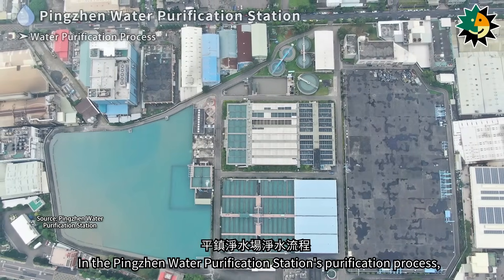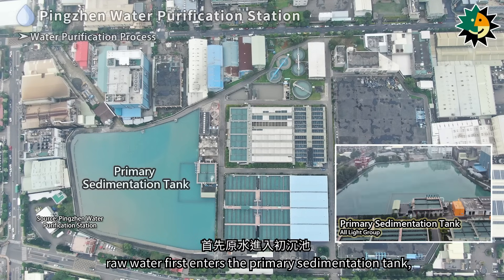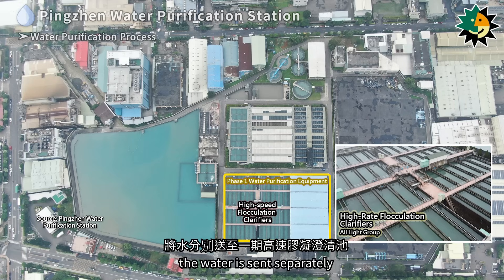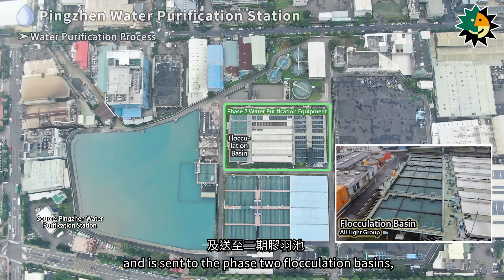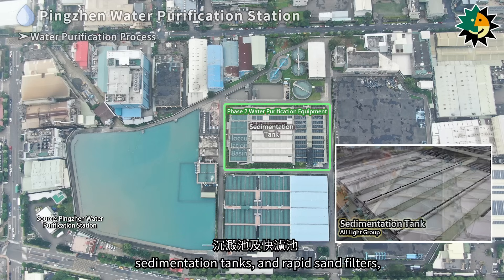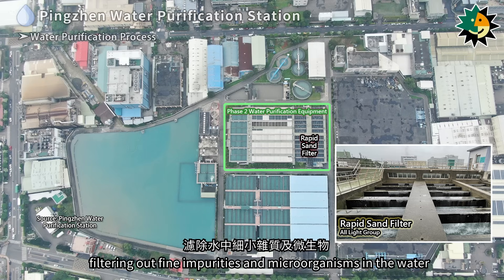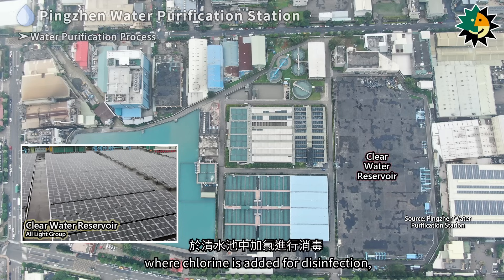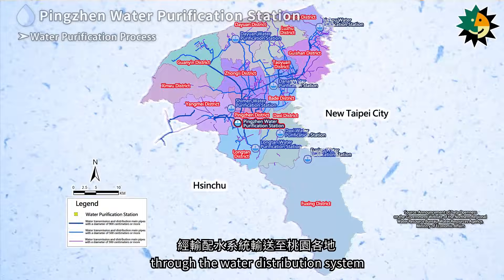In the Pingzhen water purification station's purification process, raw water first enters the primary sedimentation tank, flows through the distribution well, and after adding coagulant, the water is sent to the high-speed flocculation clarifiers of phase one. It then flows into the hardened rapid sand filters and is sent to the phase two flocculation basins, sedimentation tanks, and rapid sand filters, filtering out fine impurities and microorganisms. It then flows into the clear water reservoir, where chlorine is added for disinfection, and is distributed to various places in Taoyuan through the water distribution system.